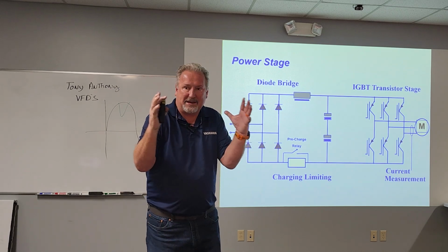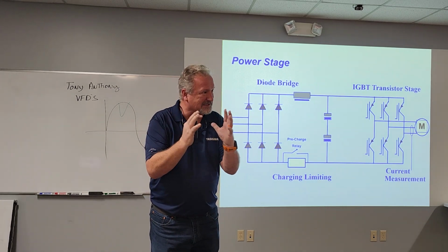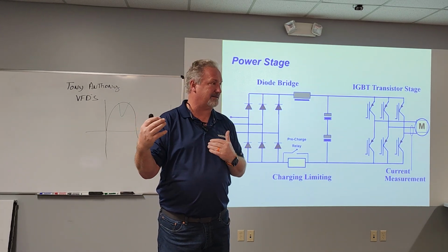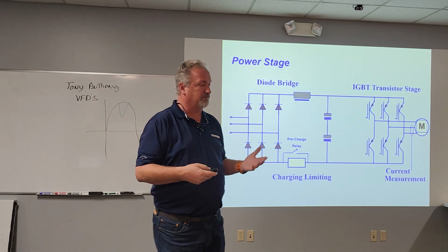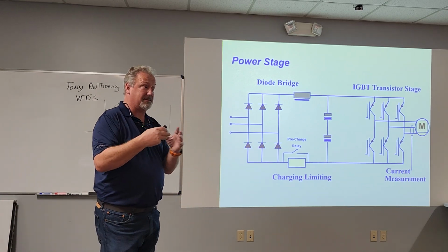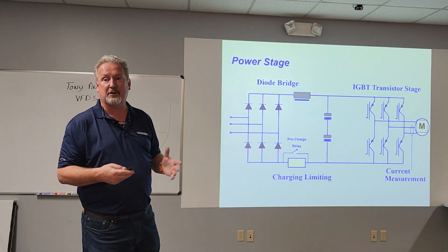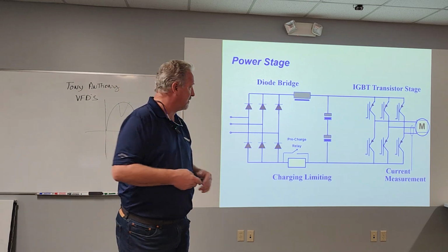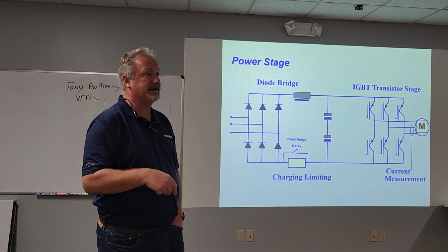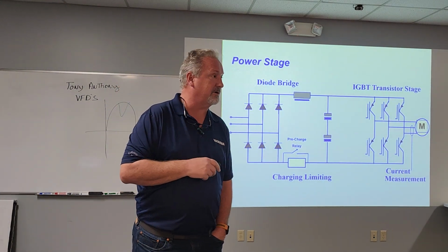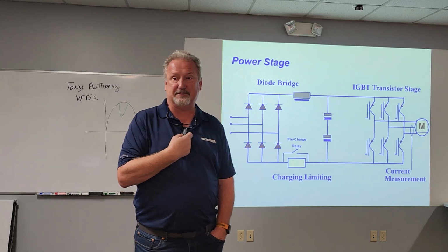Because we're making the drives smaller. Everybody wants less space. We don't have extra capacitance, so we don't have that extra. Now it's usually 2.5 to 3 times we have to upsize that drive, but we can do it. I just want to make you aware of that because you brought that up earlier. We can take single phase in and create 3-phase and run a 3-phase motor. We just got to size the drive properly.